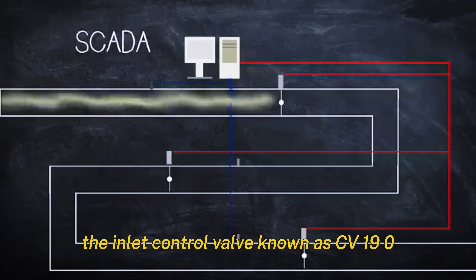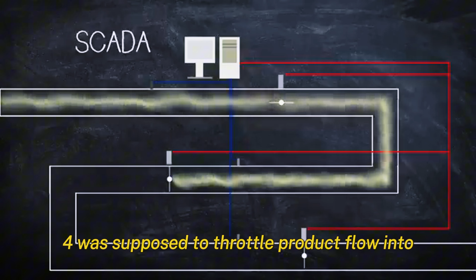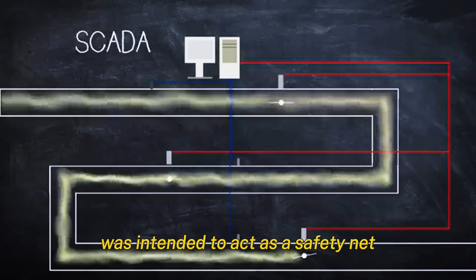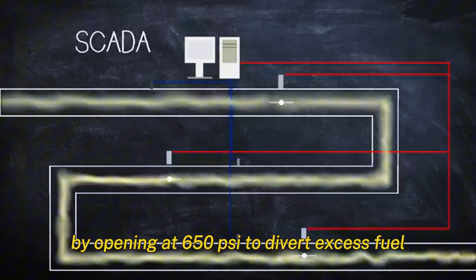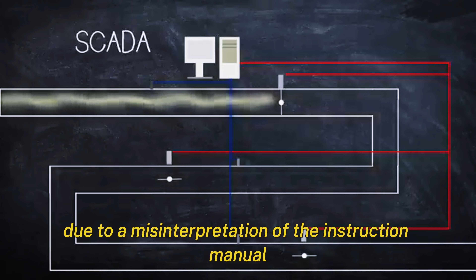The inlet control valve, known as CV1904, was supposed to throttle product flow into the terminal. Alongside it, the relief valve, RV1919, was intended to act as a safety net by opening at 650 psi to divert excess fuel. But here's where a critical mistake comes into play. Due to a misinterpretation of the instruction manual and a fatal oversight, the relief valve was set to operate at only 100 psi. It sounds absurd, but this misconfiguration would soon prove catastrophic.